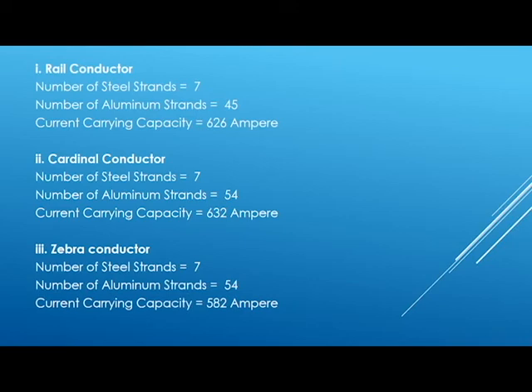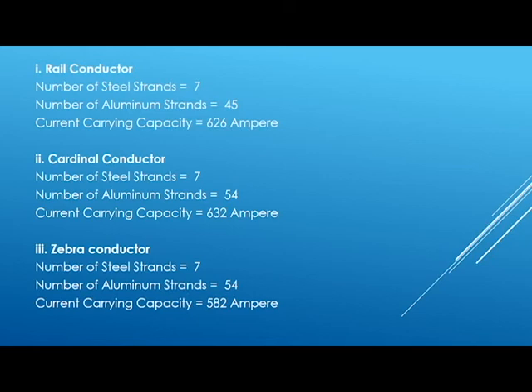Here we can observe that although the number of steel strands in Cardinal conductor and Zebra conductor is the same, there is a considerable difference between their current carrying capacities. This is because current carrying capacity not only depends on the number of strands but also on the diameter of the strand. The diameter of the strands in Cardinal conductor is higher compared to Zebra conductor, which is why Cardinal has a higher current carrying capacity.